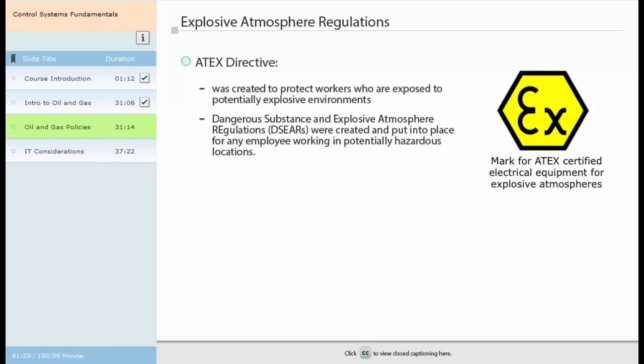ATEX, derived from the French term atmosphères explosives, consists of two European directives created to protect workers who are exposed to potentially explosive environments. From the ATEX directives, the Dangerous Substances and Explosive Atmospheres Regulations, or DSEAR, were created and put into place for any employee working in a potentially hazardous location. The regulations mandate that equipment and safety control systems are certified for explosive atmospheres and marked accordingly.